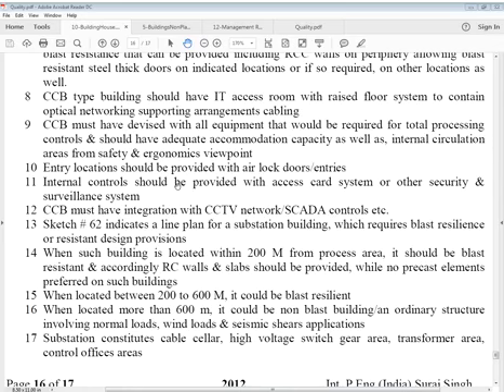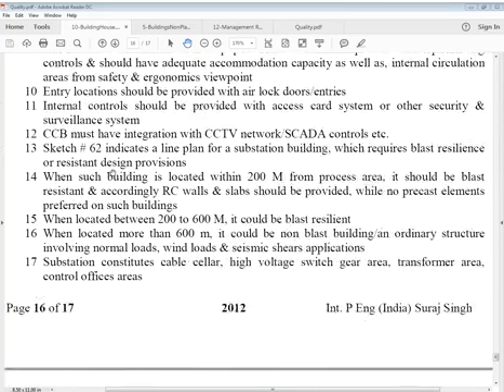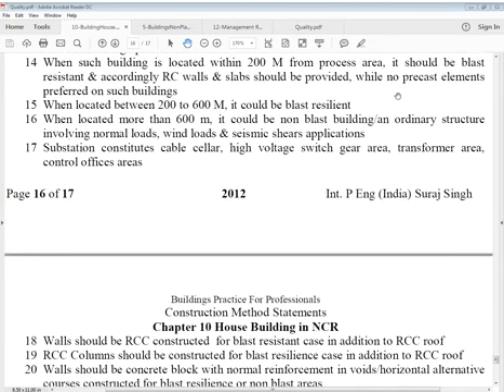Then there's a sketch giving the line plan for a substation building, which requires blast resistant or blast resilient design. When such a building is located within 200 meters from the process area, it should be blast resistant, and RCC walls and slabs should be provided, with no precast elements preferred on such buildings. When located between 200 to 600 meters, it should be blast resilient. And when located more than 600 meters from the process area, it could be a non-blast building, an ordinary structure involving normal loads, wind loads, and seismic shear applications.